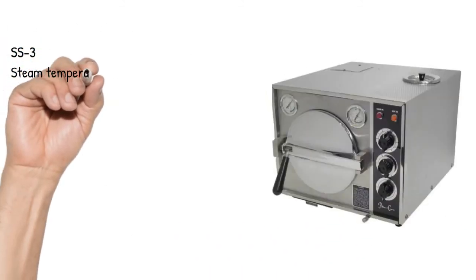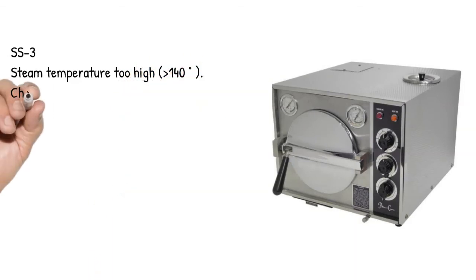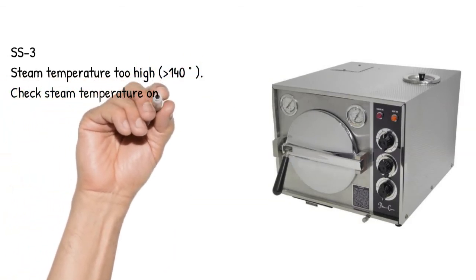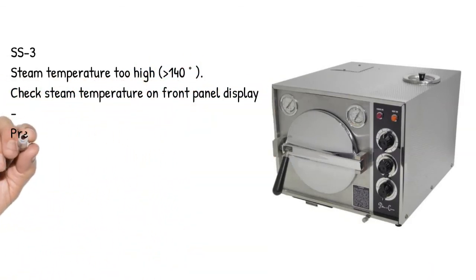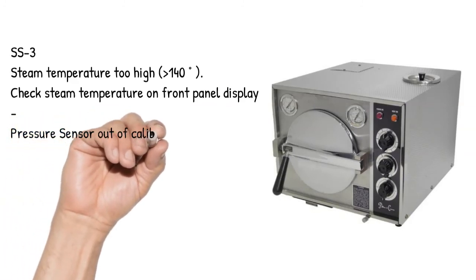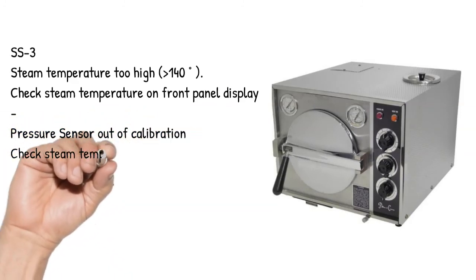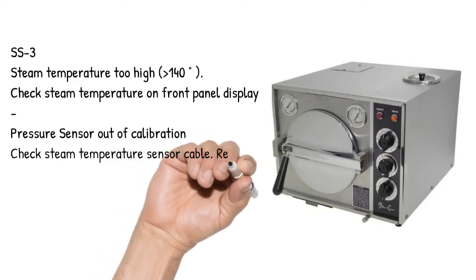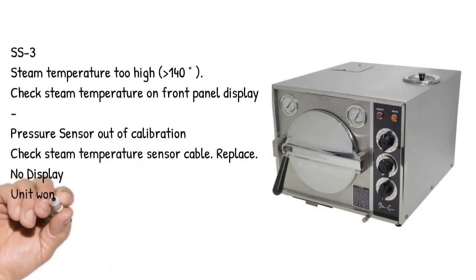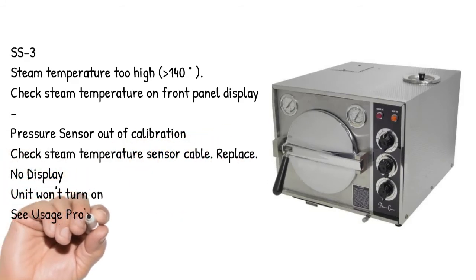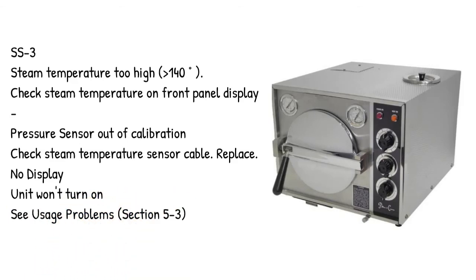SS3. Steam temperature too high, greater than 140 degrees. Check steam temperature on front panel display. Pressure sensor out of calibration. Check steam temperature sensor cable. Replace. No display. Unit won't turn on. See usage problems, section 5-3.